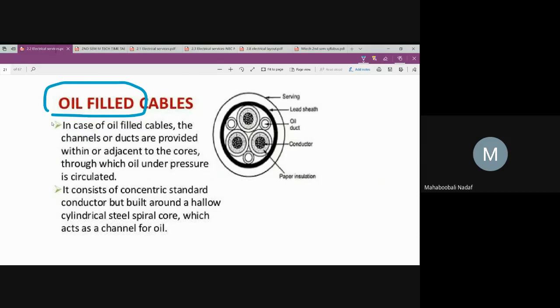These are generally given oil filled cables. Now see here, this central portion is conductor, and there is insulation for each conductor. So there are other voids, and these voids or ducts are filled with oil. This is the composition or cross section you can see.